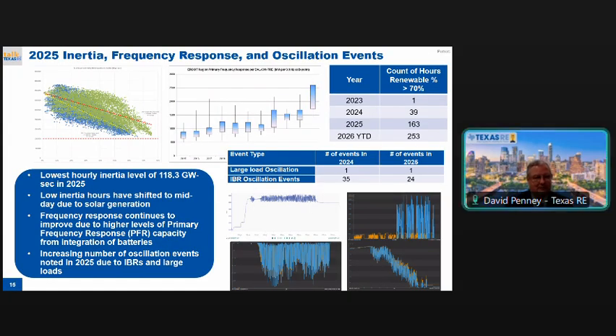One of my favorite topics is related to inertia and frequency response, and we're definitely starting to see some trends in the inertia area. Inertia historically has been a very slow moving trend as the resource mix changes, but since the resource mix is starting to change more rapidly, we're starting to see some more rapid changes related to inertia. The chart in the upper left-hand corner has inertia on the vertical axis and the percentage of load that's served by renewables on the horizontal axis. The horizontal dotted line at the 100,000 mark is the critical inertia level that ERCOT has calculated to be able to withstand a BAL3 type contingency event. So it's a line we don't want to cross.